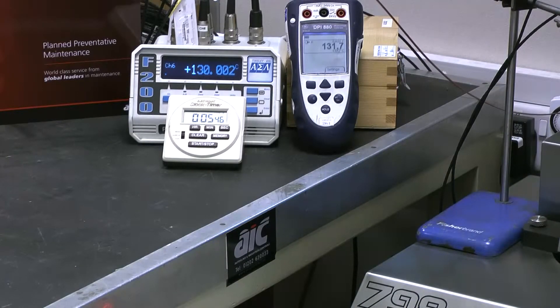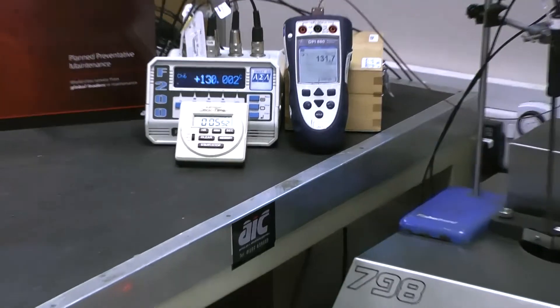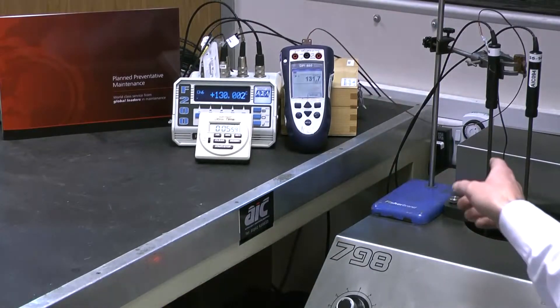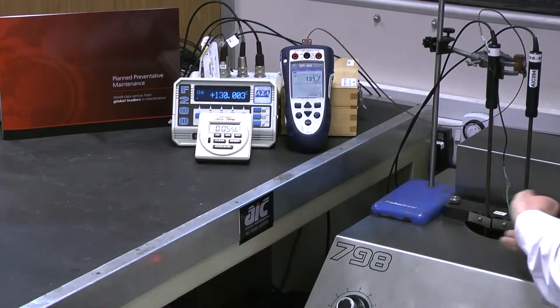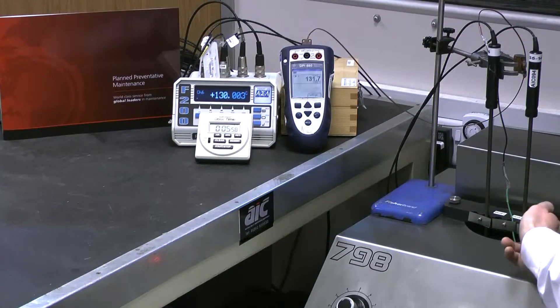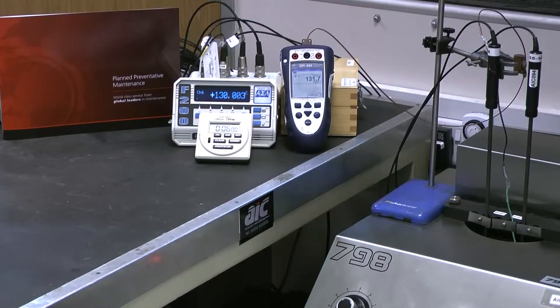And the calibrator is now reading 131 degrees. Again, because now the Type J cable does not have temperature gradient, or very little, almost all of the temperature gradient is in the Type K thermocouple, and that's the cable we need to know the character of in order to get an accurate measurement.